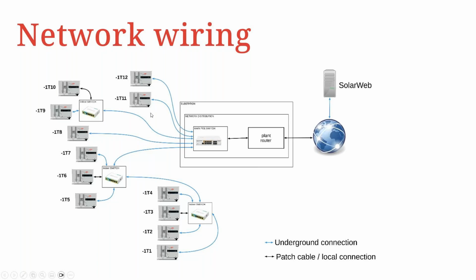Still talking about network wiring, there are cases where you would have inverters at further distances than expected in terms of the range coverable with the LAN switch. If that is the case, it is important to connect repeaters. These repeaters or amplifiers make it possible for seamless communication with all the Tauros in the system. For the Tauro, the connection range is 100 meters per communication link. So if you have anything beyond 100 meters, it is advised or recommended that you have a repeater switch that would be able to amplify the signal coming from these inverters.